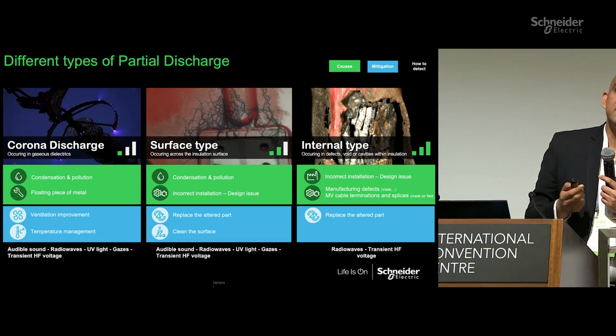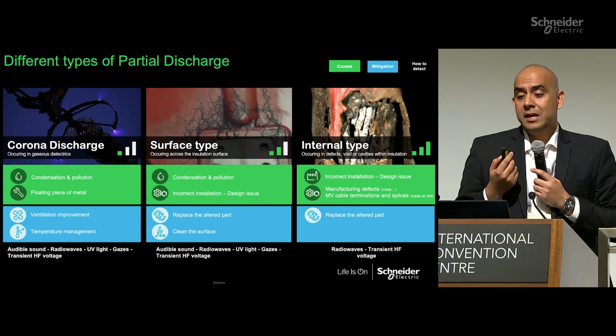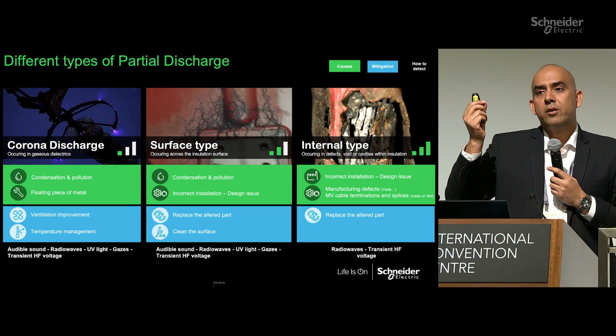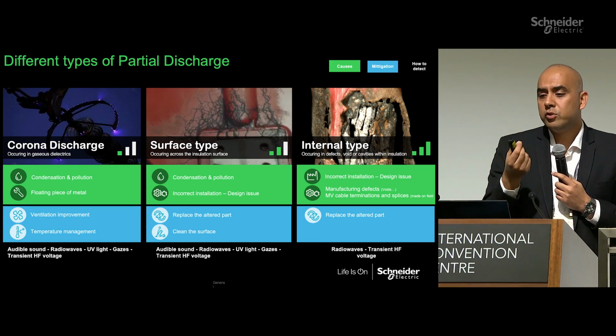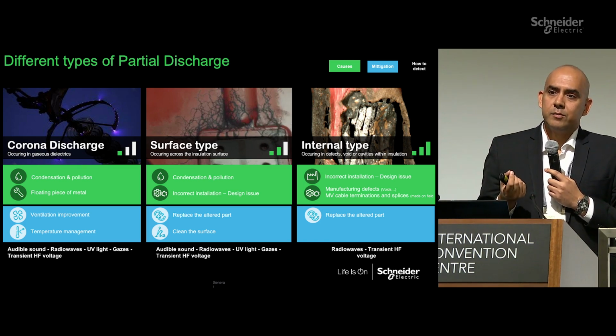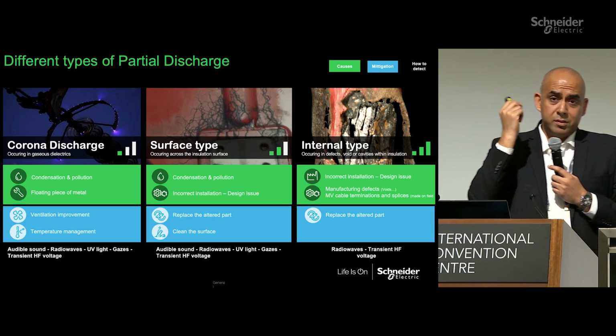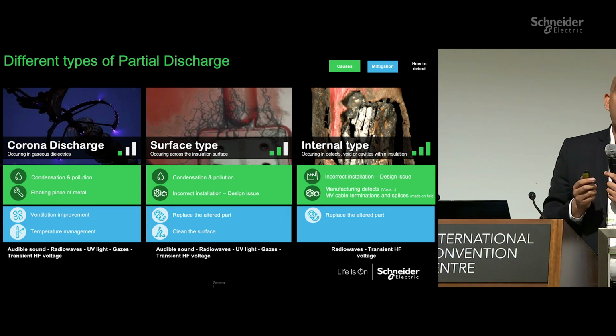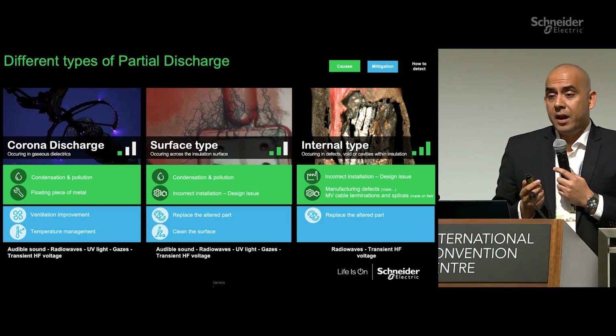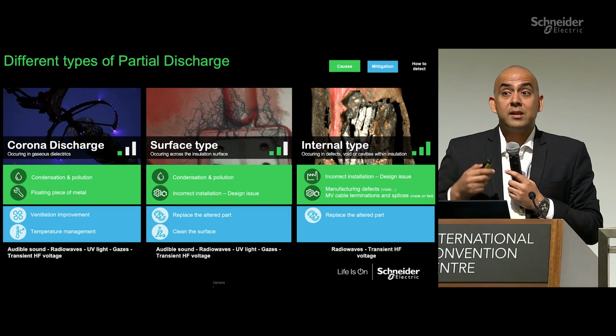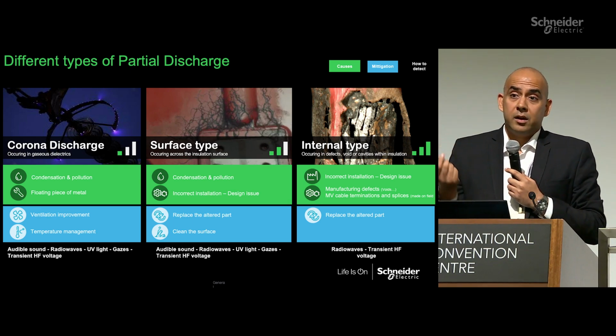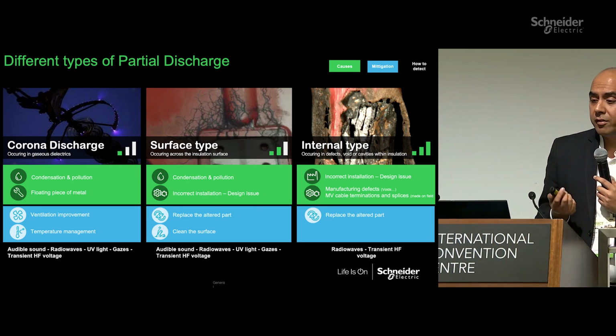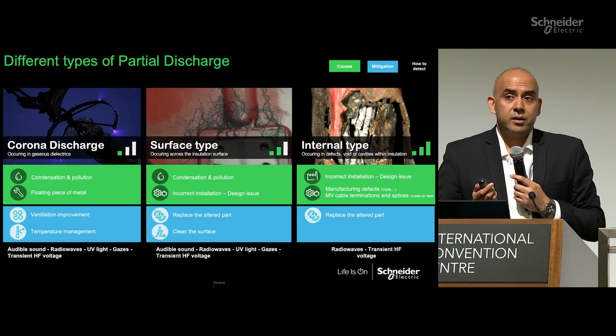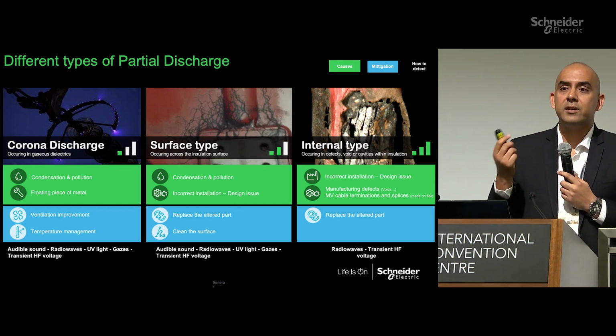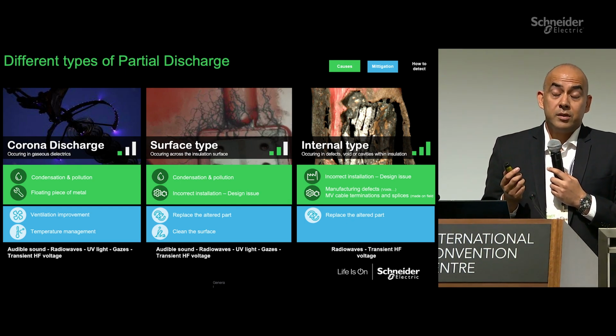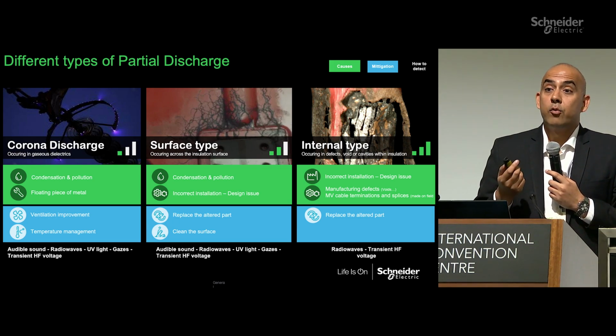The third and the most dangerous type of discharges is the internal ones, which happen because of internal issues inside the insulation systems. It could be micro holes, some cracks, etc., which come in, and they often do not get detected. And it could be because of incorrect installation, some issues in manufacturing or design, improper cable terminations, etc. And the only solution here is you need to replace the part. If the partial discharge is an internal type, there is no other solution. You cannot mitigate this without replacing the part.